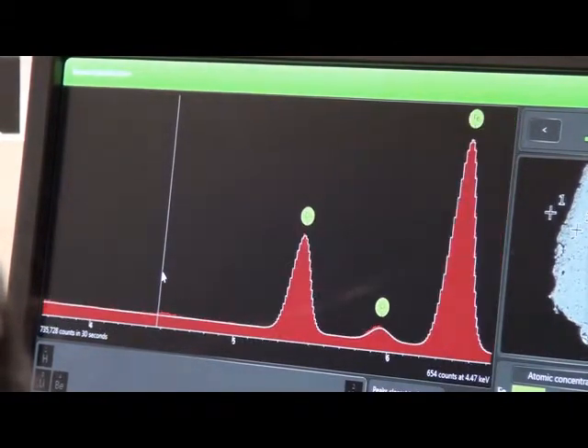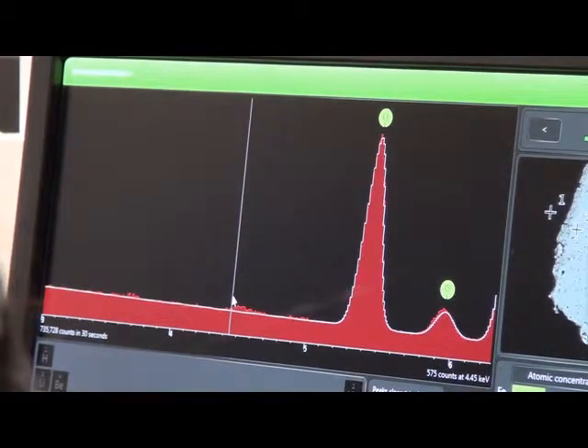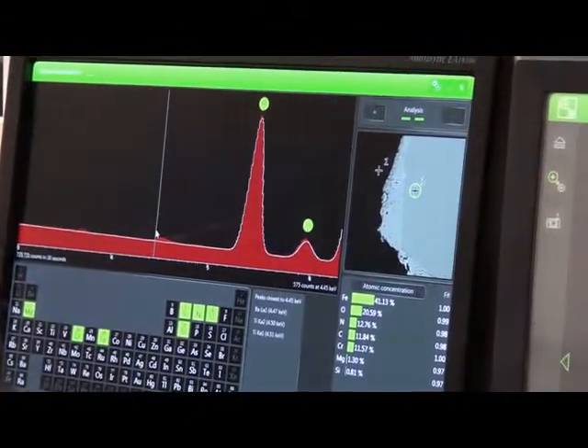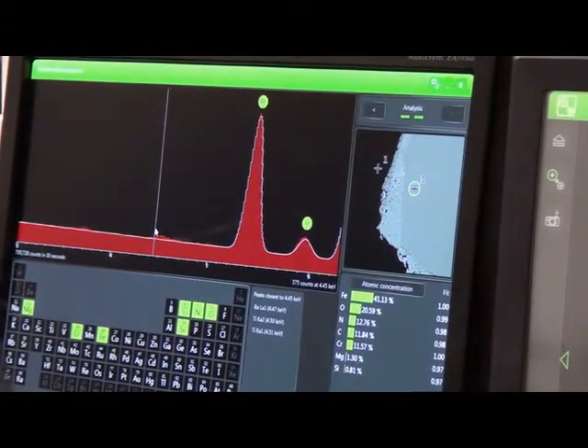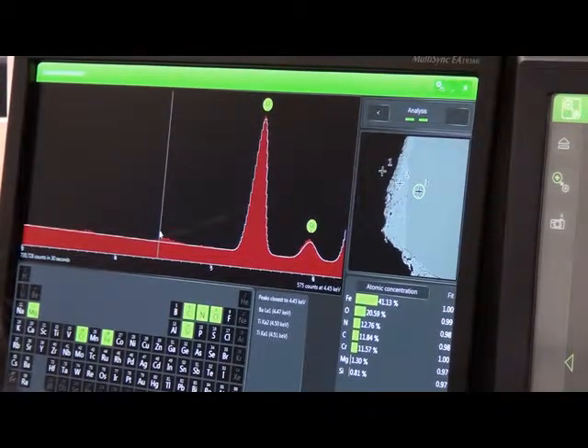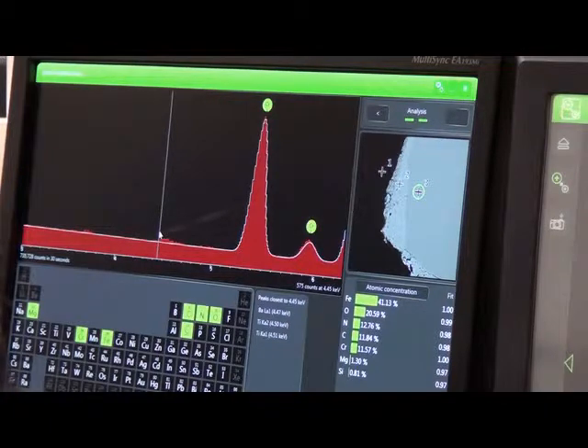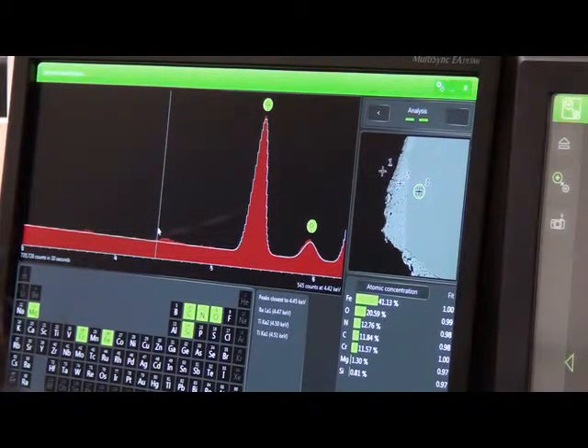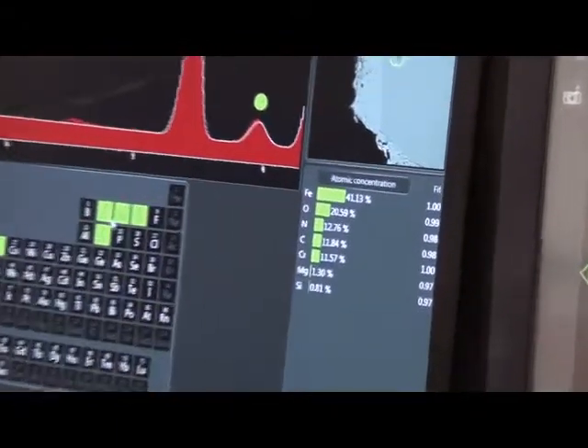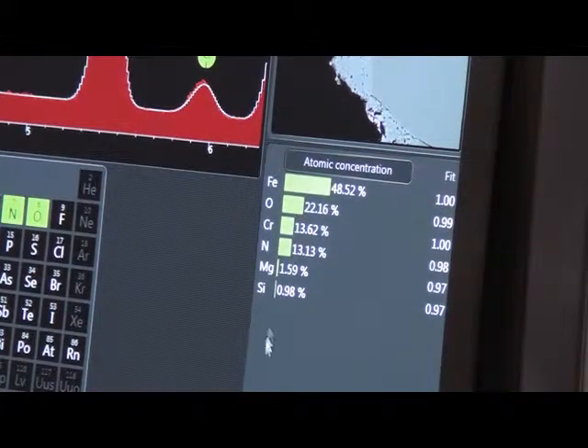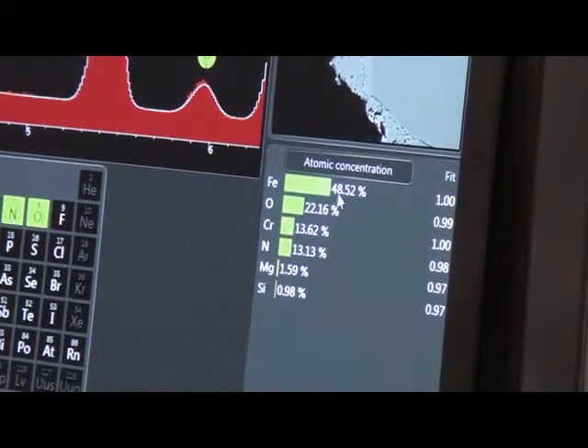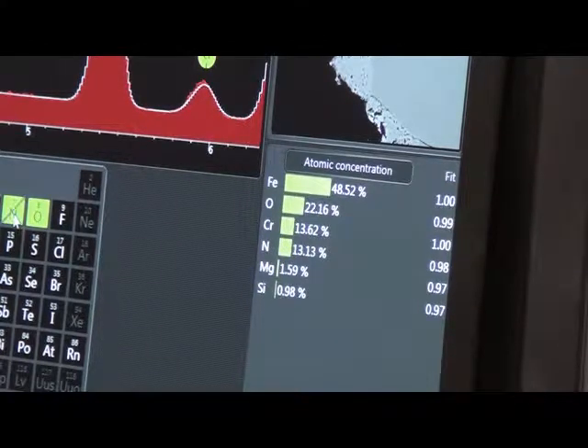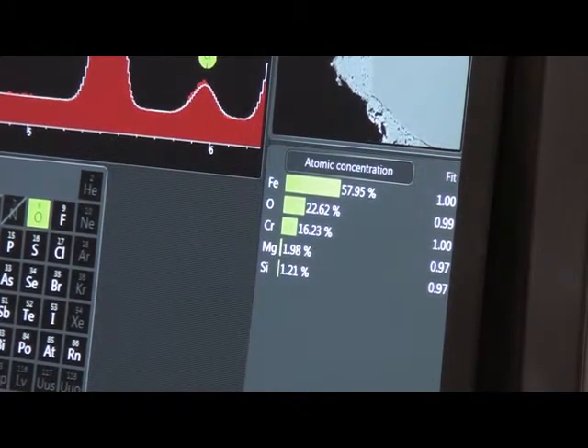And so with more counting time and with more electrons, you are actually better able to see things that are present in small amounts. So one of the things to remember when we're doing analysis is that you want to have as much current as we can do. And you also might want to consider the amount of counting time. Because here you can see it's actually in this is a carbon-coated sample. So that's why it's detecting carbon. But it actually will do a more precise job and can be capable of finding other elements present.